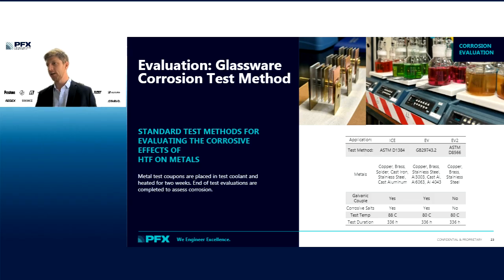What we're looking at here is an ASTM D1384 bundle with copper, solder, brass, steel, cast iron, and cast aluminum. These bundles are then placed into a vessel that contains coolant. They're heated to a specific temperature. They may or may not include corrosive salts to accelerate the rate of corrosion. And then they're held for 2 weeks. And then at the end of the test, we tear it down.